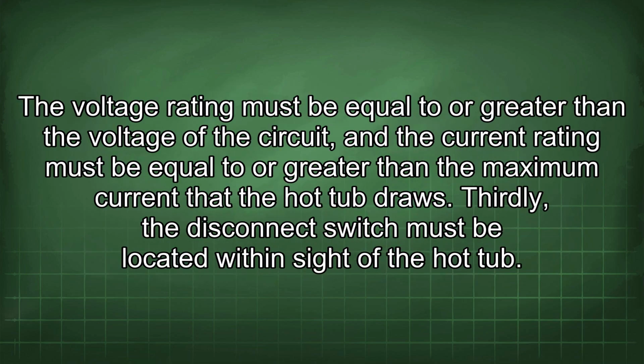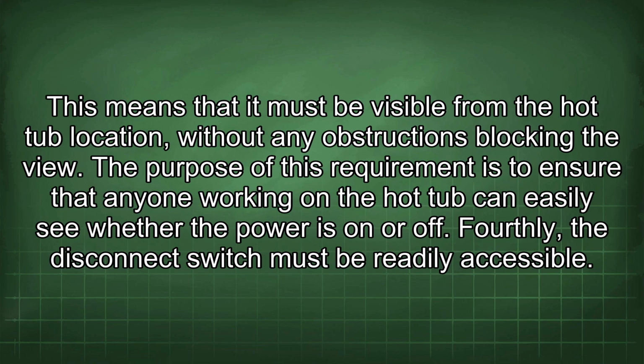The voltage rating must be equal to or greater than the voltage of the circuit, and the current rating must be equal to or greater than the maximum current that the hot tub draws. Thirdly, the disconnect switch must be located within sight of the hot tub. This means that it must be visible from the hot tub location without any obstructions blocking the view. The purpose of this requirement is to ensure that anyone working on the hot tub can easily see whether the power is on or off.